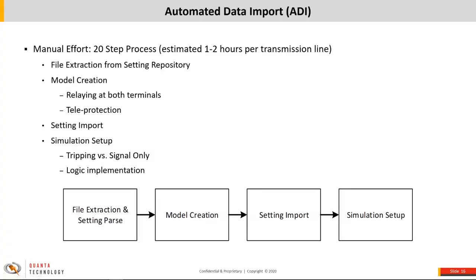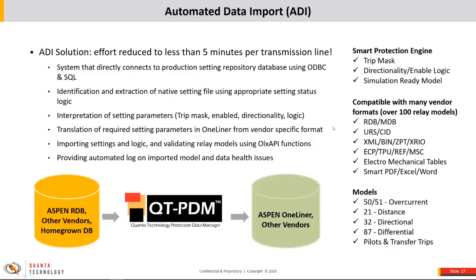The manual effort of modeling all the protections on a transmission line can take about one to two hours. You first need to extract settings from your setting repositories — sometimes multiple packages. You need to create the models, which for teleprotection is highly manual, then import the settings. You'd also normally test your settings by applying a few faults and checking that signal-only and tripping elements are correctly set.